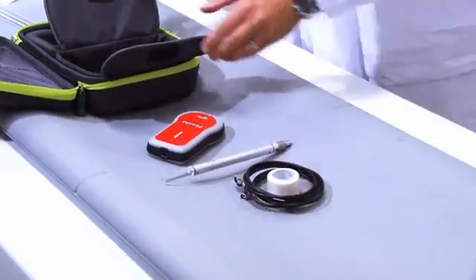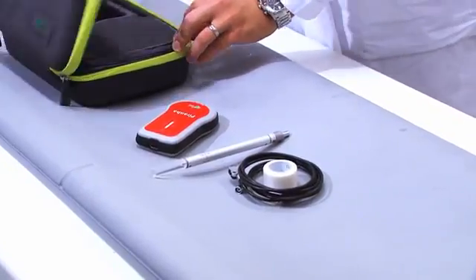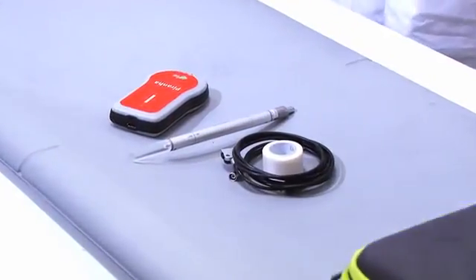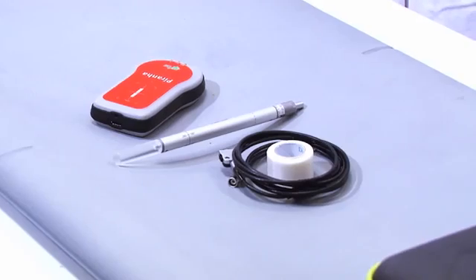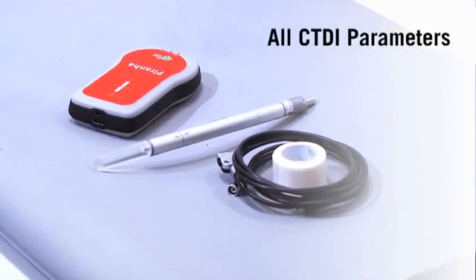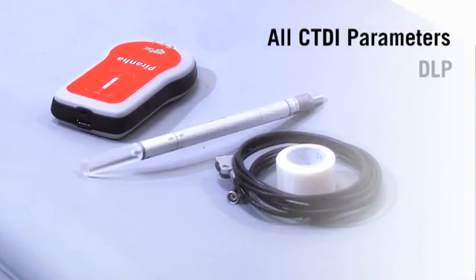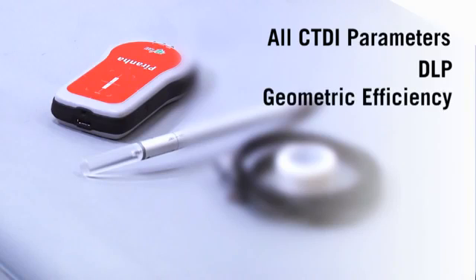The CT dose profiler will, in just one shot, give you a complete picture of the dose profile and it can also give you all CT dose index parameters, dose length product, geometric efficiency and full width at half maximum.